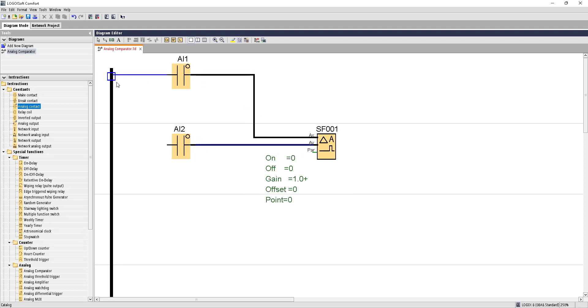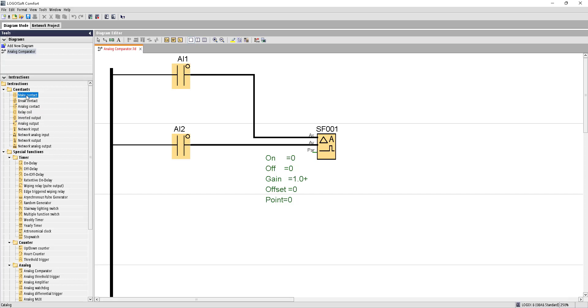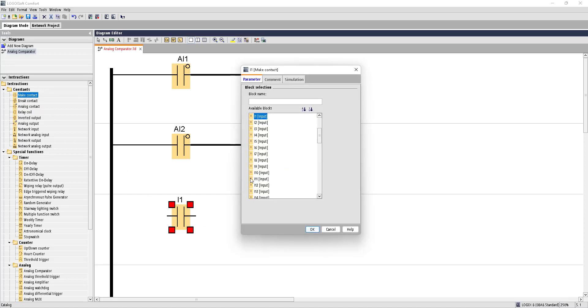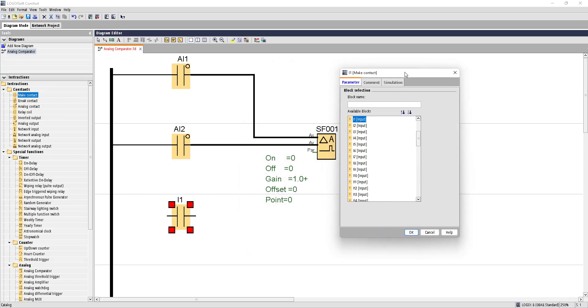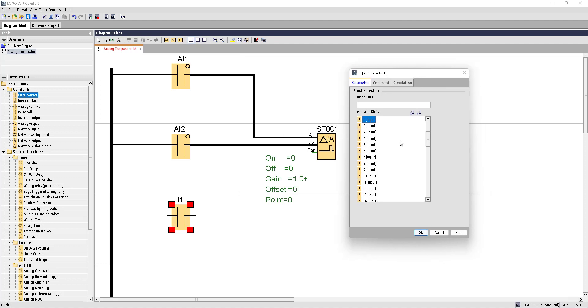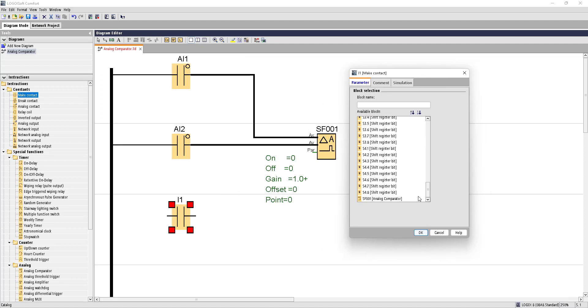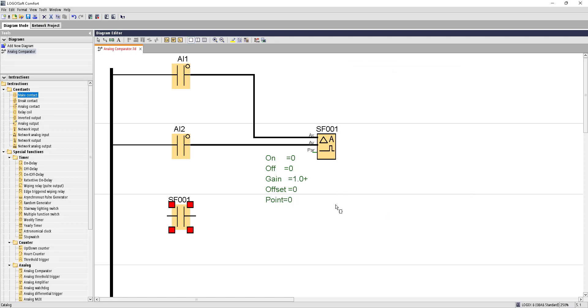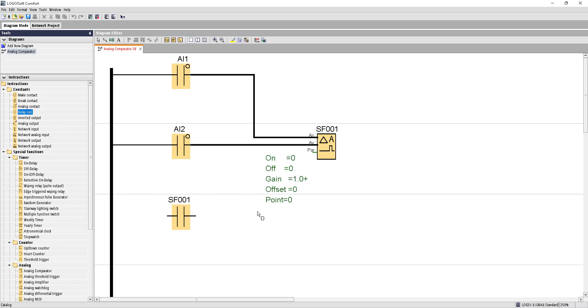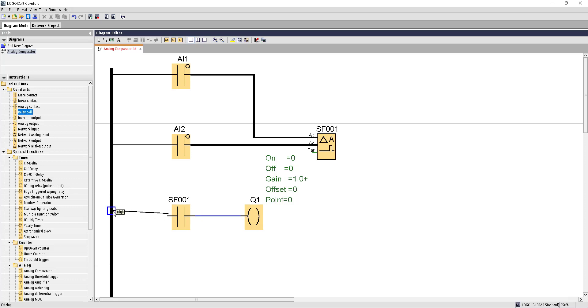Let's connect them to AX and AY, and also connect them to the power rail. Now suppose you want to turn on a contact based on this comparison. For that reason, we'll need to bring a make contact, and this make contact would be the contact of SF001. Choose this one, and it will be the contact of our analog comparator. Let's also bring in a relay coil that would be activated based on the logic given here. So this is the circuit. Now let's configure the comparator.